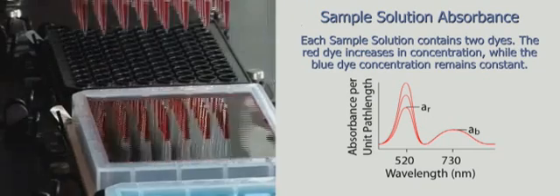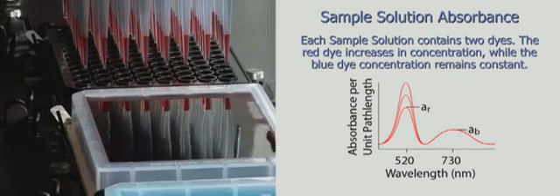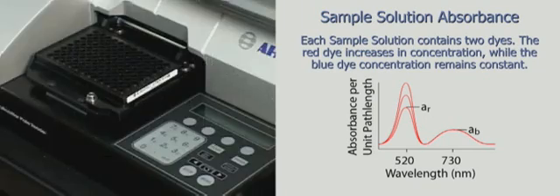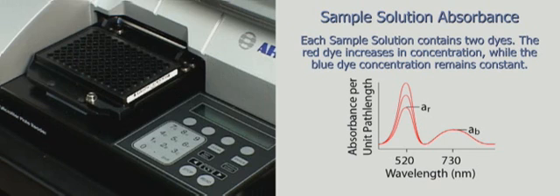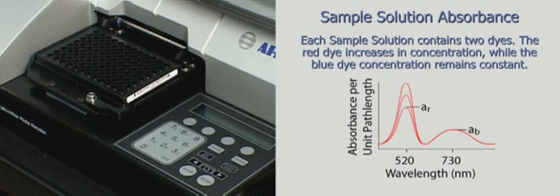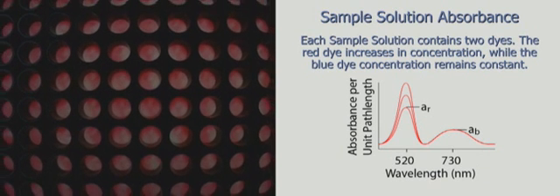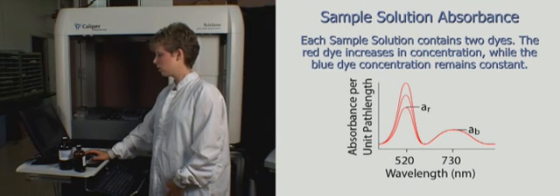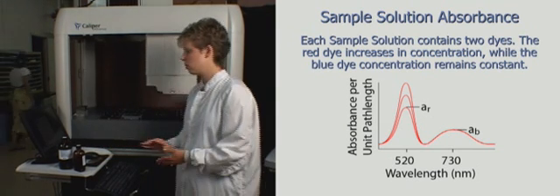Sample solution is added to the diluent solution. Then, ratiometric calculations are used to individually determine the volume dispensed from each individual channel into each well of a microtiter plate. This ratiometric process enables a degree of performance measurement not possible with just one dye and one wavelength.